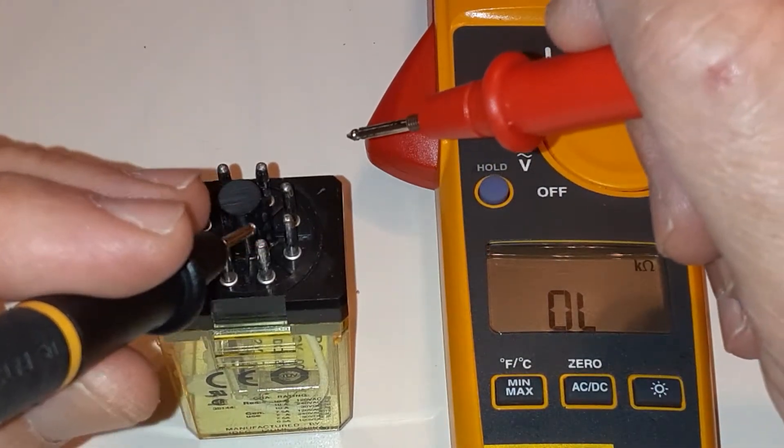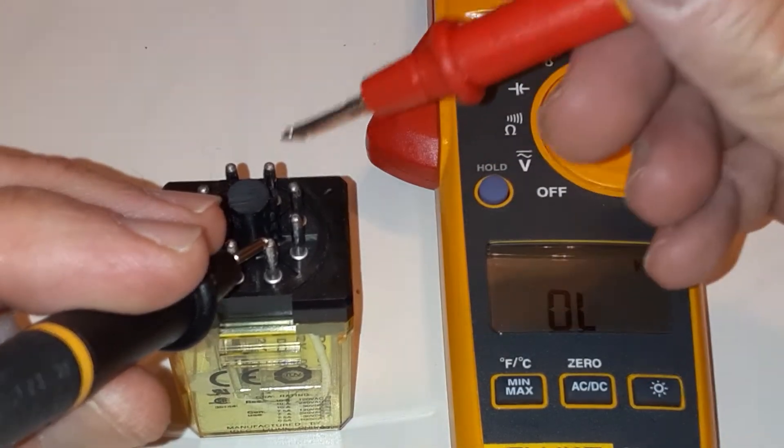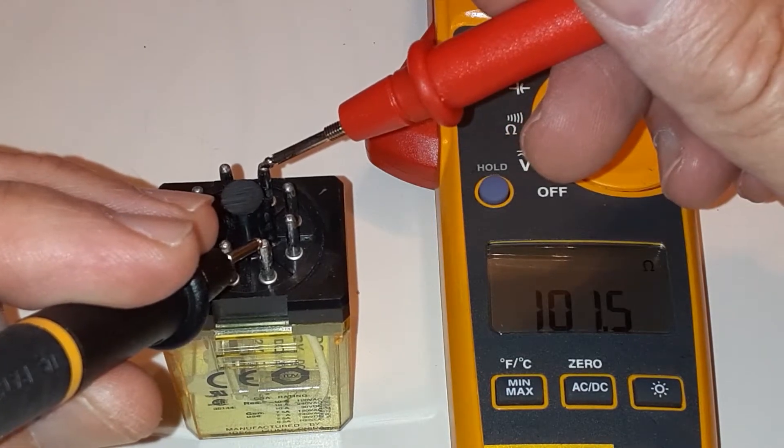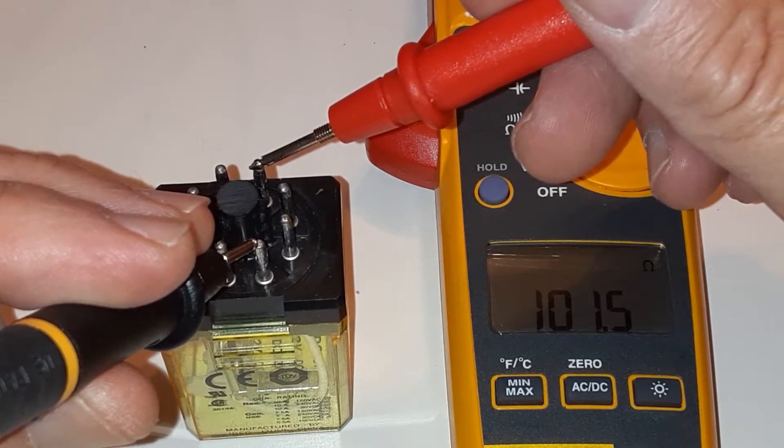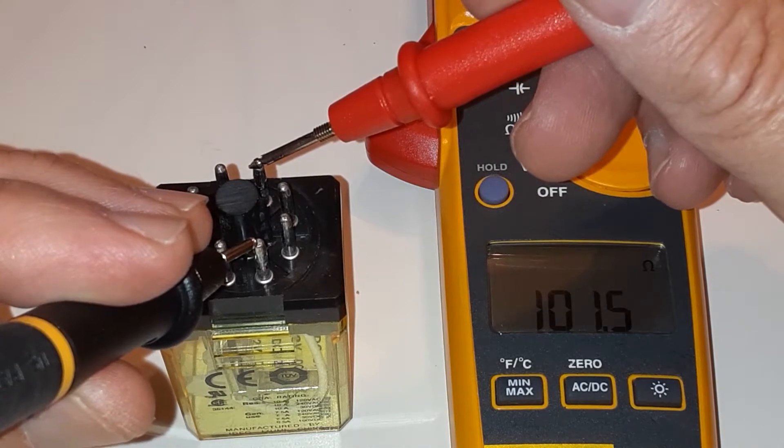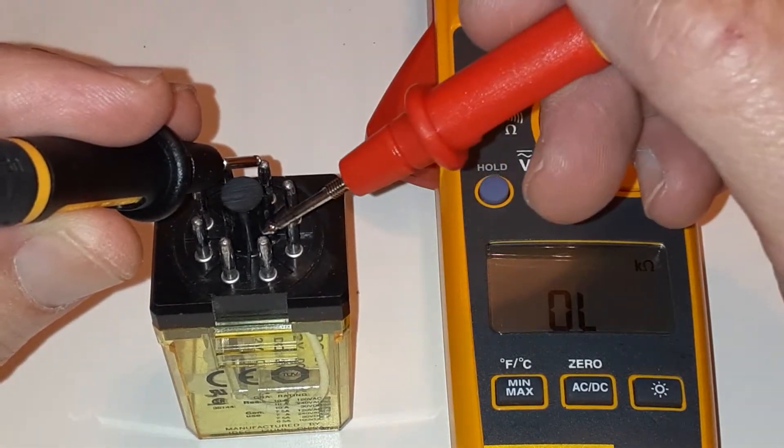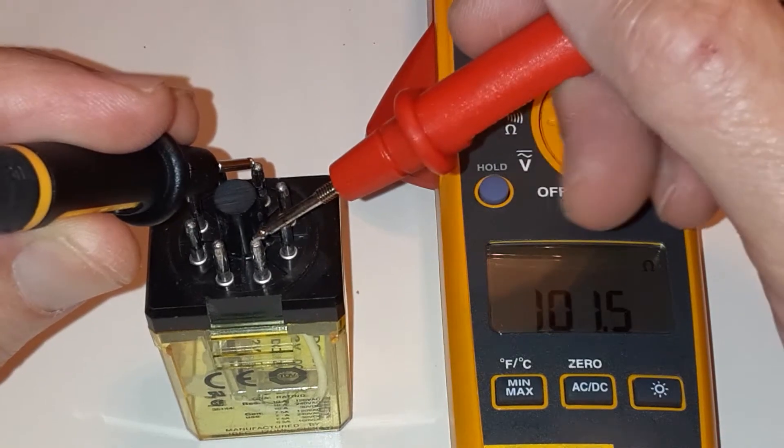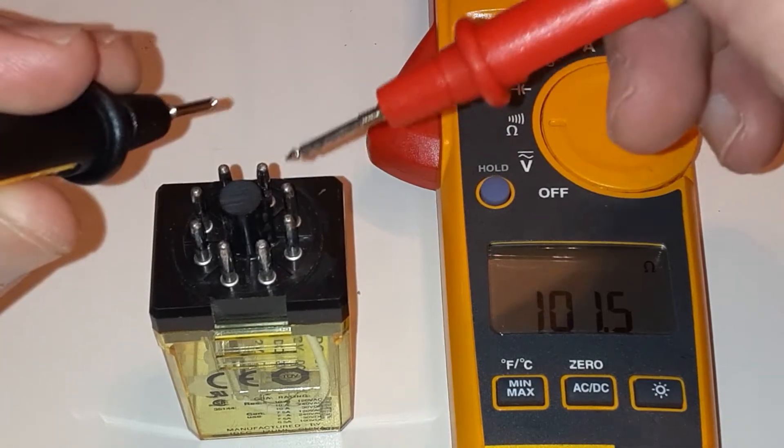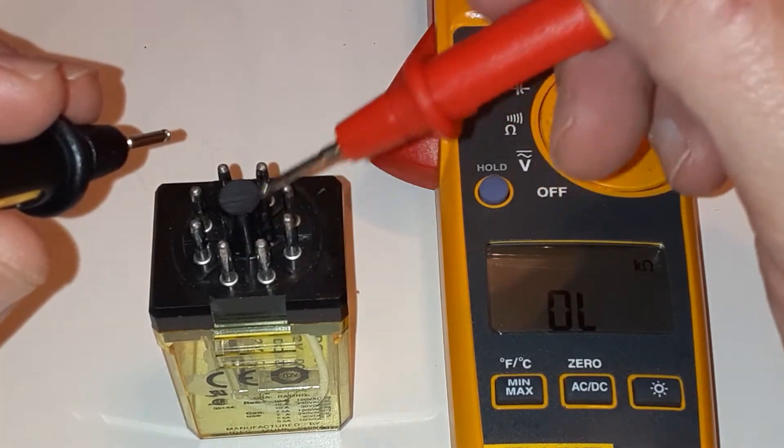Let me go across those terminals and see if I get a reading. 101.5. So that's coil resistance. Let me switch the wires around to show that it doesn't matter which way I take the measurement. 101.5. That's my coil connection right there.